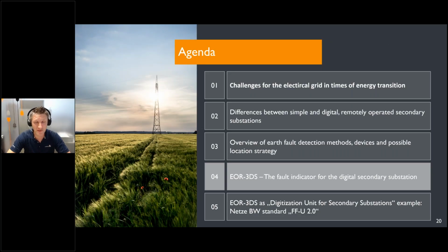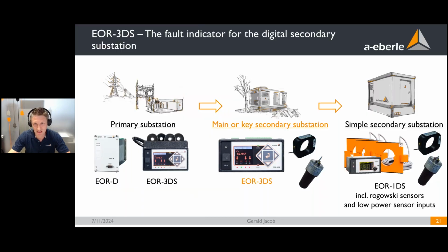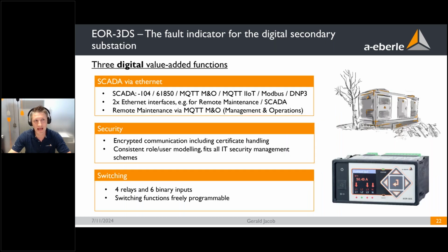Okay, I hope this overview helps you to see the demand for these earth fault detection devices. And now we come to the advantages of the EOR3DS compared to an EOR1DS in the application of a digital secondary substation. So the EOR3DS, as you can see, is also capable of low power sensors, and it has 3 digital value-added functions, as we call them. On the one hand, the device has not only a serial protocol like Modbus RTU, it has this as well. It has a lot more serial protocols like 101, 103, DNP via RS485. This is all possible, but it also has a lot of different SCADA protocols based on Ethernet.